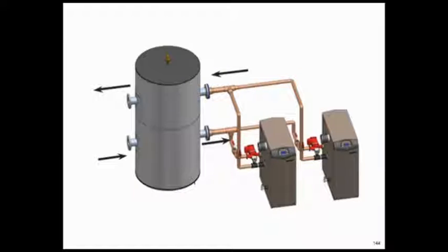By putting all this together, you might need a buffer tank when you do these calculations to get the extra gallons. Again, if it's a water tube boiler, you probably will need that buffer tank because there's very little water in the boilers to begin with. If you have a fire tube boiler, it has a lot more water, but we still need to do the calculations. We've got to sit down and calculate it and make sure. Again, delta T and the volume are the key. What delta T you're going to set your boilers on to cut on and off. On, off, delta T. That's the key to how many BTUs you can store to handle a short cycle. The higher the delta T and/or the higher the volume of gallons of water, the longer the runtime I can get, and the more I can kill the cycling issue.